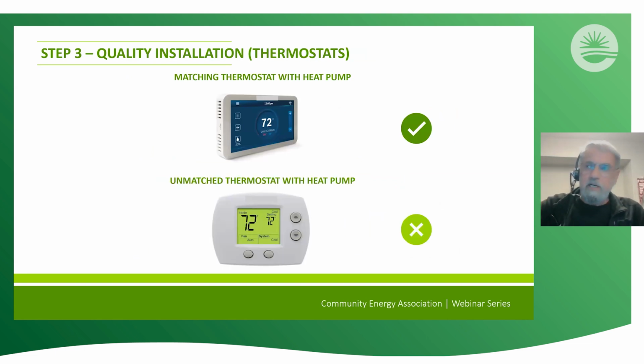Thermostats. There are companies out there that have really figured out how to brand their products directly to homeowners. They do a really good job of that. What I would say is that you're better off to ignore all of that. What you really want to do is get whatever thermostat that manufacturer recommends goes with their product. You'll have two general categories of equipment, and it's basically communicating and non-communicating. Communicating is usually the top tier of brands and models that they offer. What that means is that there are all kinds of algorithms built into the equipment that communicate conditions with sensors between the thermostat and the actual equipment outside and in your mech room. And that is the most effective way to optimize performance, comfort, everything.